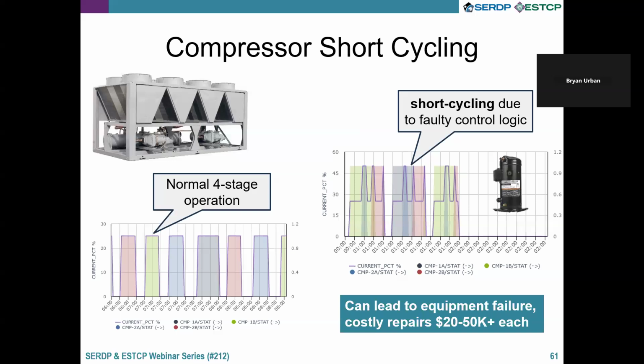And so here the compressors were coming on and off for a minute or two at a time, which is really bad for compressor lifetime. It can shorten the lifespan and cause compressor failure. This site actually had some compressor failures in the year before, and it cost 20 to 50K to get them replaced. So if you can detect this and prevent it, you can avoid costly repairs on your equipment.